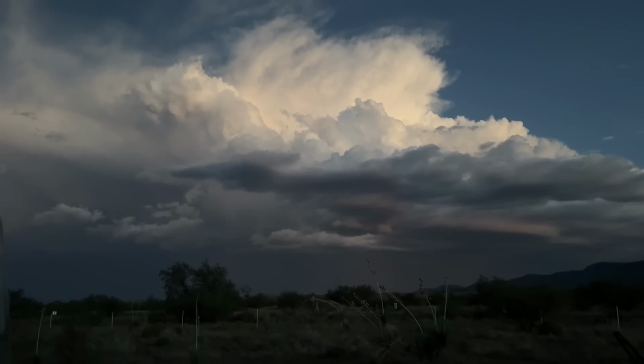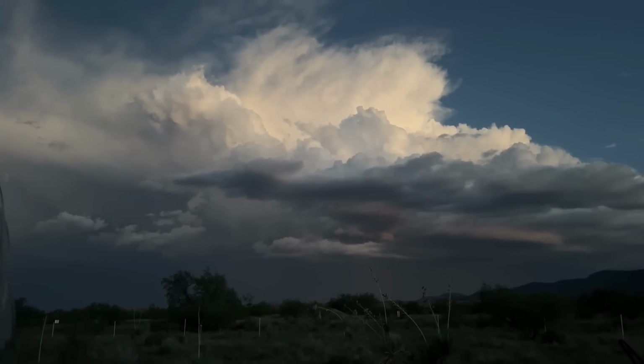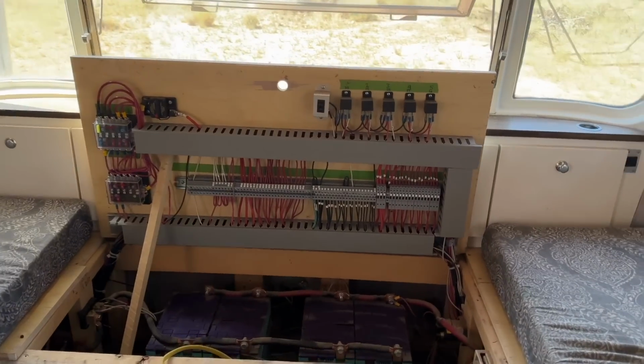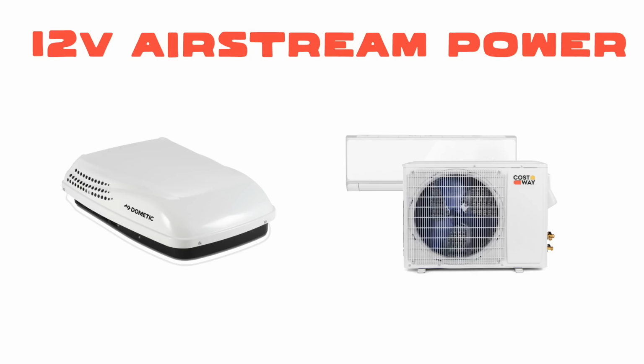Even better, if we have a big storm coming in and we're worried about lightning, we can cut the 30 amp power to the trailer and just run the mini split for hours off our 400 amp hour lithium battery bank built into the RV. Win, win, win. Just for reference, on our 12 volt system, that rooftop air conditioner would use 150 amps, which would have drained the batteries in no time. The mini split averages about 50 to 55 amps.